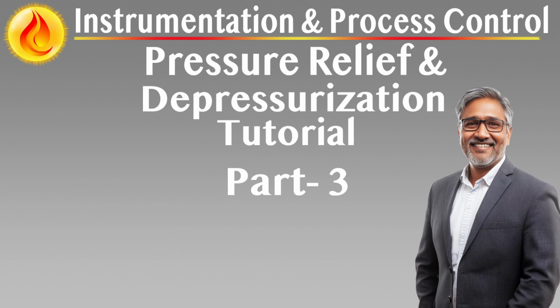Depressurization device location. The location of depressurization valves follows the same general principles as relief valves, with a focus on minimizing pressure drop, avoiding obstructions, and ensuring effective isolation of each depressurization zone. Best practices include installing depressurization valves as close as possible to the equipment or piping section being protected. Valves may discharge into the same flare or vent system as associated relief valves, provided the system is designed to accommodate the combined flow.